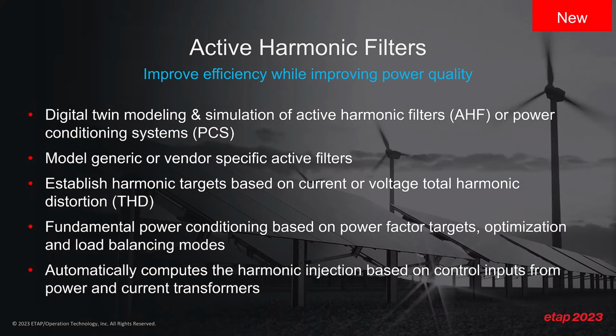So let's take a look at what we've done in ETAP for active harmonic filters. Of course, we are providing the ability for digital twin modeling and simulation of active harmonic filters, or power conditioning systems, PCSs. And we've included two models, a generic model and vendor specific active filters. We've started with Schneider Electric AccuSine filters as our first vendor specific active filter. And our active harmonic filter in ETAP can establish harmonic targets based on current or voltage distortion. It can also provide fundamental power conditioning based on power factor targets and load balancing modes. And it has the ability to automatically compute the harmonic injection that is required based on the location of our current transformer, as I discussed in the quick concepts.